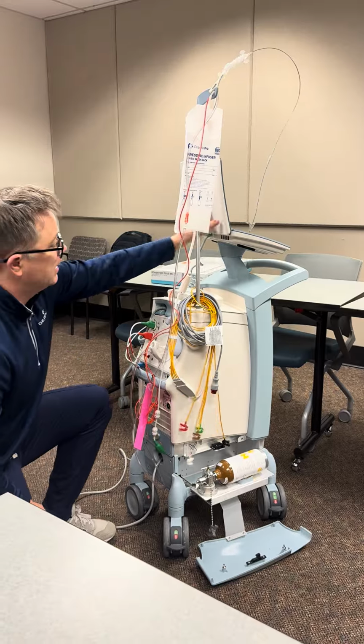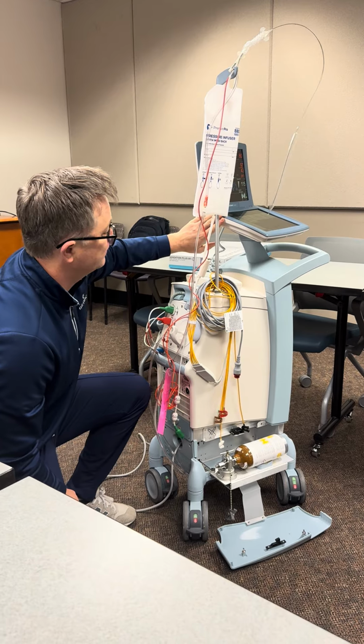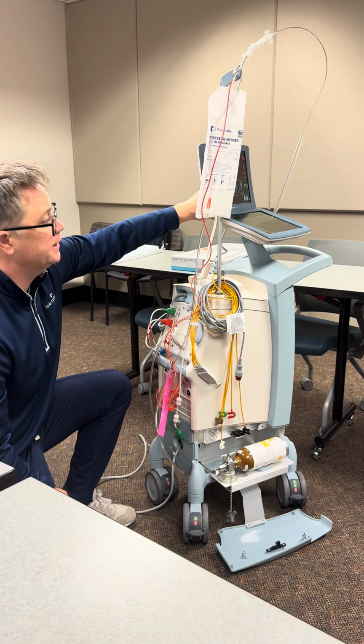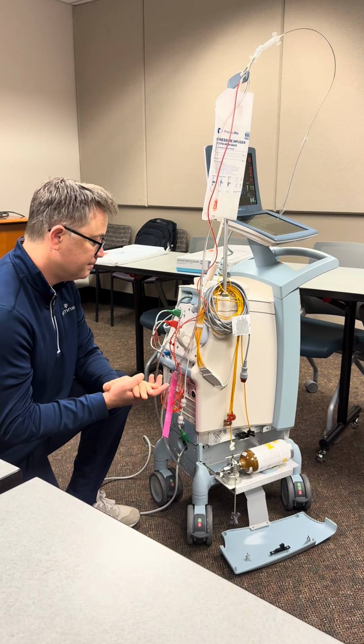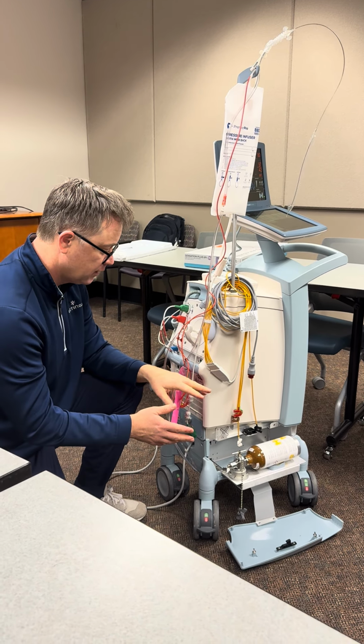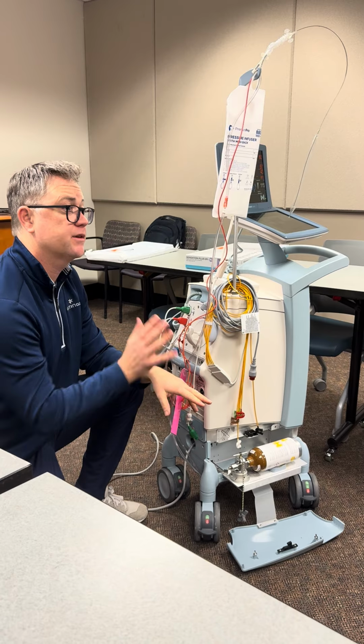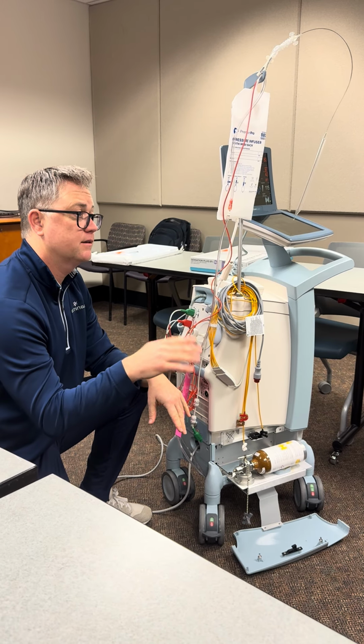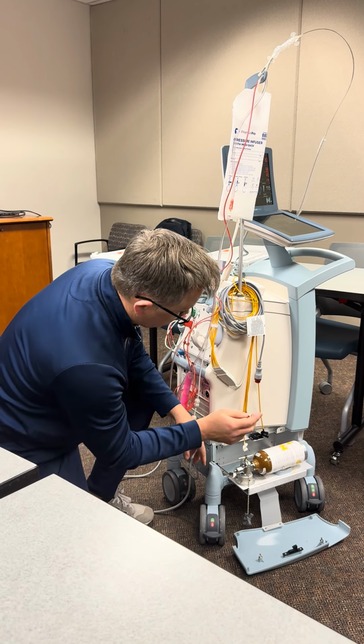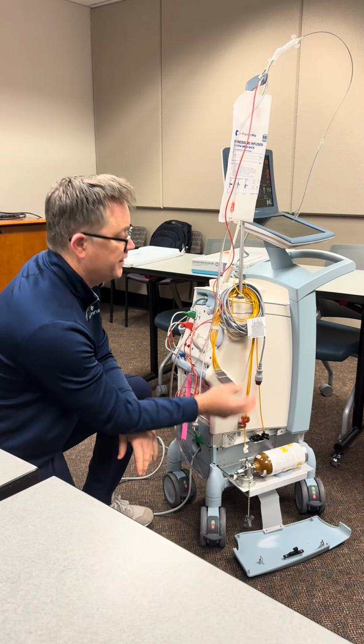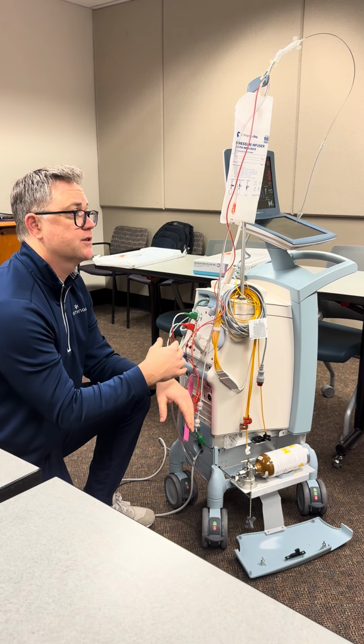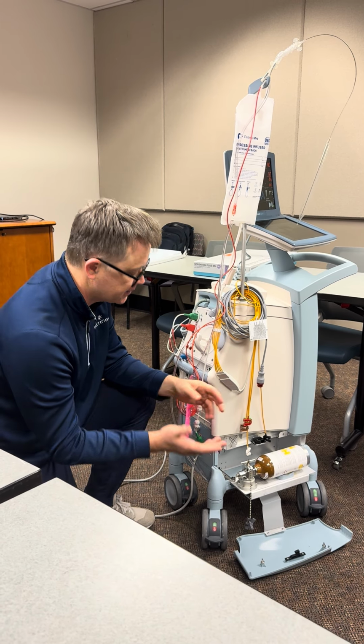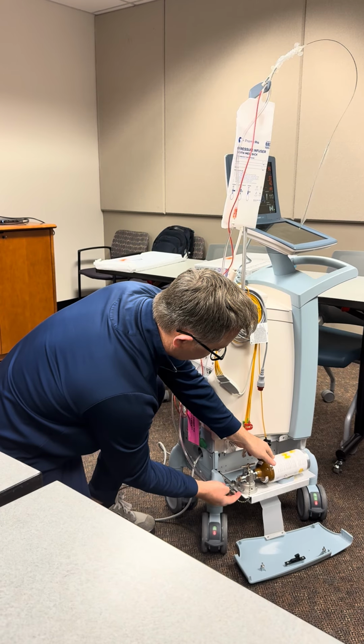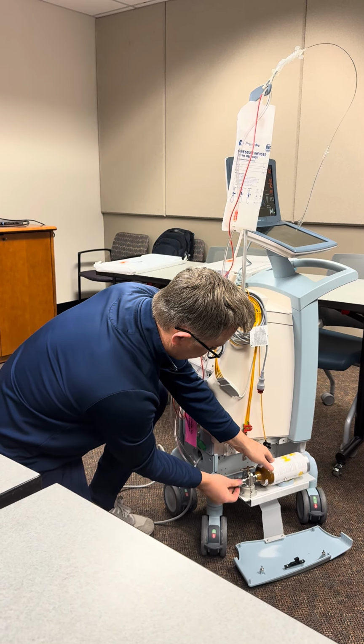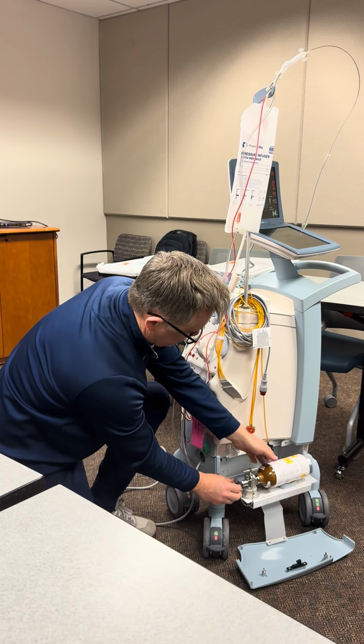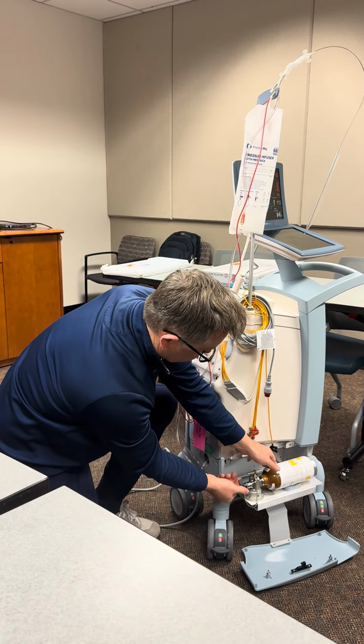So there's a couple days of helium left in here. Once you get a low helium alarm on here, you've got what we call 24 autofill. So you've got a couple days' worth of helium in the machine once you get that low helium alarm. That's because we've got this little transport mode that has a little reservoir in it that contains extra helium. To change a tank, because we have about a quarter of a tank, I'm going to turn this tank off so we don't lose it.